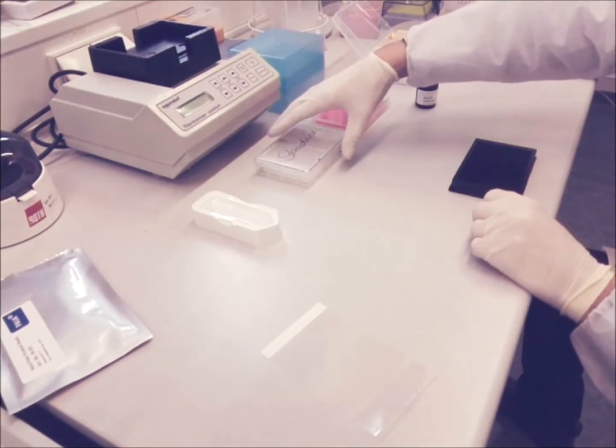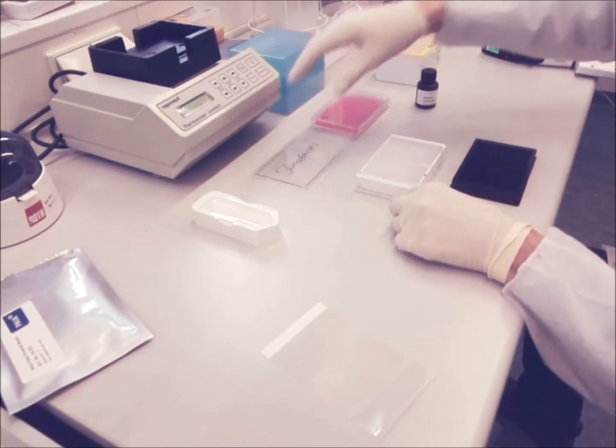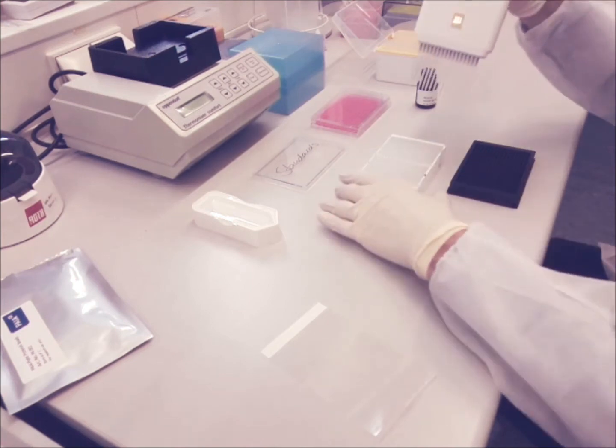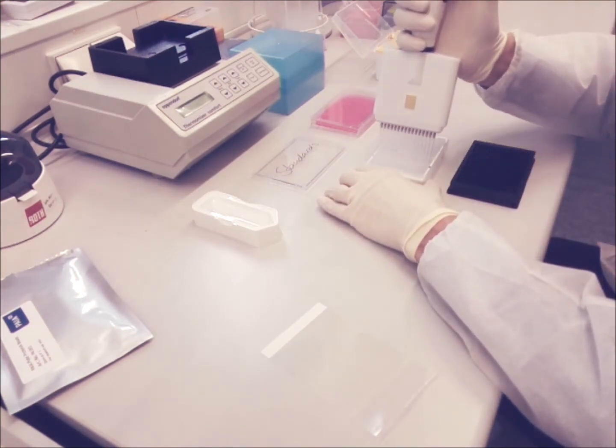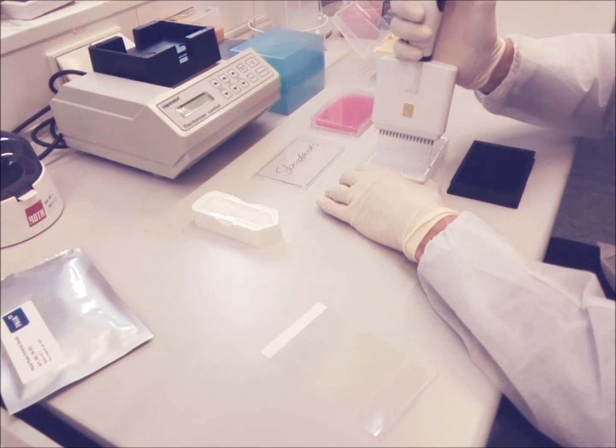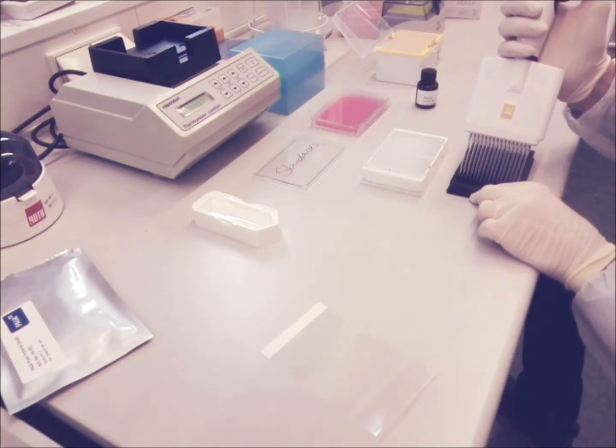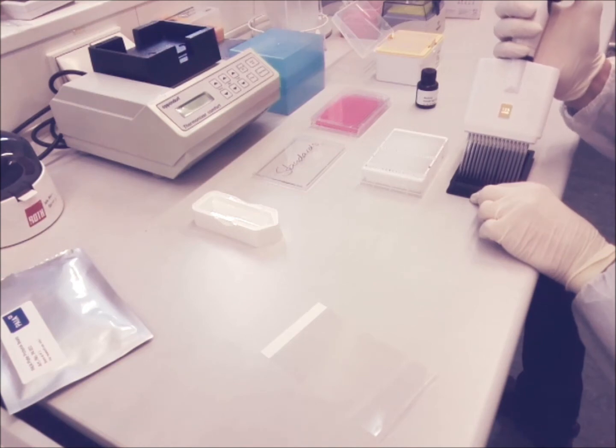Now we are adding the calibration standards to the first 3 rows. We recommend preparing at least 10 calibration standards for the generation of a reliable calibration curve. For optimal results, it is advisable to prepare the standards in the same matrix as the samples.